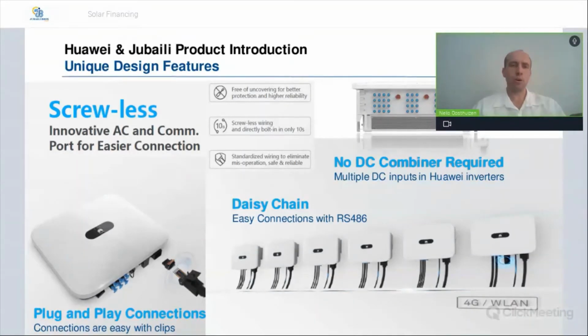Then moving on to the Huawei inverters' ease of installation. The Huawei inverters have some unique design features. First of all, they've got multiple MPPTs, so there's no need for a DC combiner box. Then it's easy to daisy chain the inverters on the communication side with RS485. And then they've got easy plug and play connections, so you don't need to unscrew a lot of covers before you can start connecting. The connection points are available in the plug and play configuration on the bottom side of the inverter.